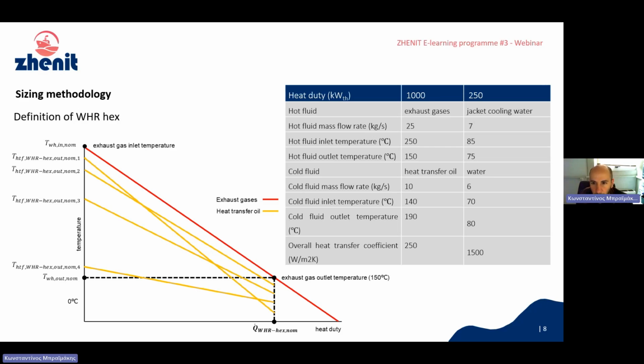And in our simulations, we have considered, based on data that we have from vessels, that in the case of the exhaust gases waste heat recovery we have a very large heat duty of about 1 megawatt, and we have 250 kilowatts for the low temperature waste heat recovery heat exchanger from jacket cooling water. And these are some temperature ranges. For example, in the exhaust gases, we have a maximum temperature of the oil that is about 190 degrees, and the oil enters at 140 degrees. And in the case of the jacket cooling water, we have lower temperatures that are between 70 and 80 degrees. So after determining all these conditions that correspond to the nominal point, we size this heat exchanger and we estimate its area.